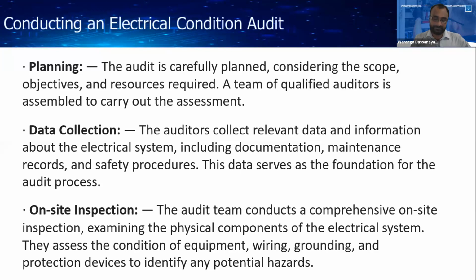Then on-site inspection. The first thing is you have to inspect the system. As I mentioned in the previous session, the introduction to electrical systems, you have to inspect one by one whether proper distribution boards are installed and whether the cable installation methods are okay. Like that, one by one, you visually inspect and record any fault.